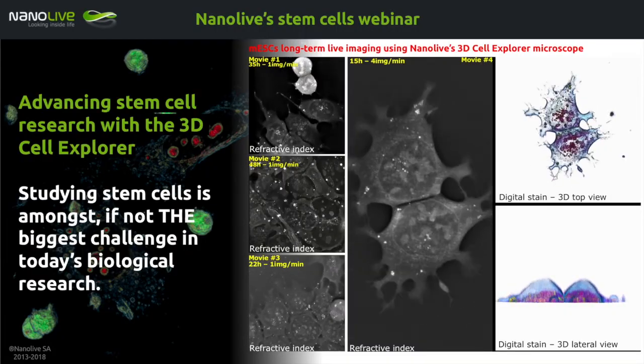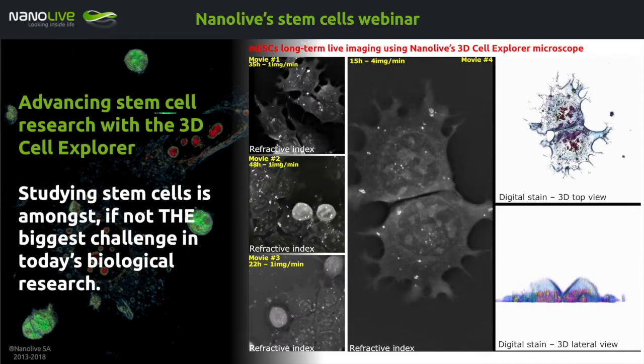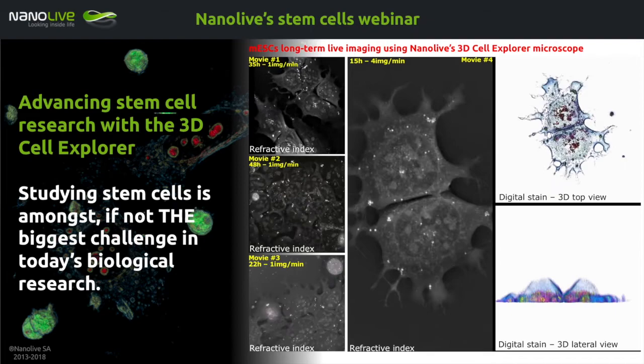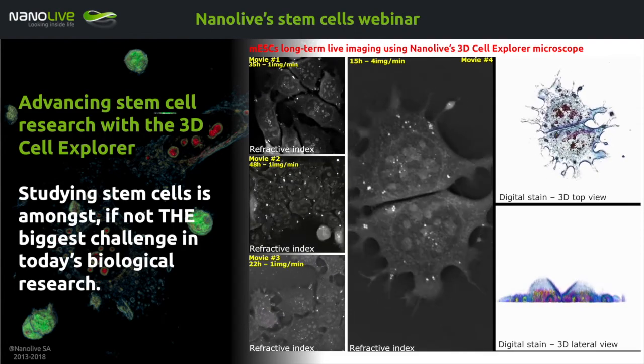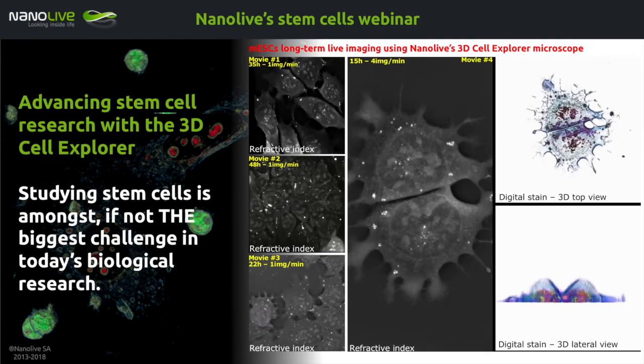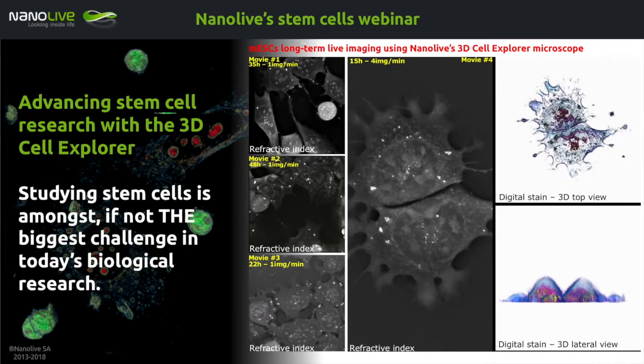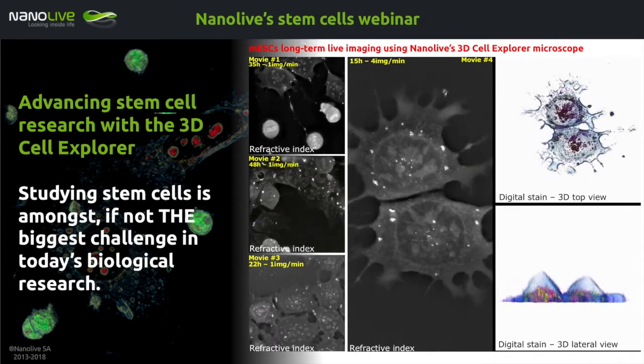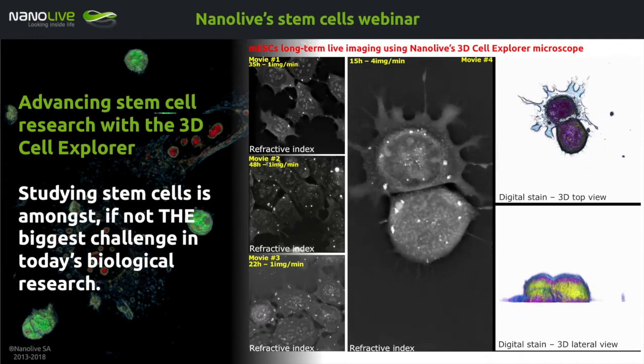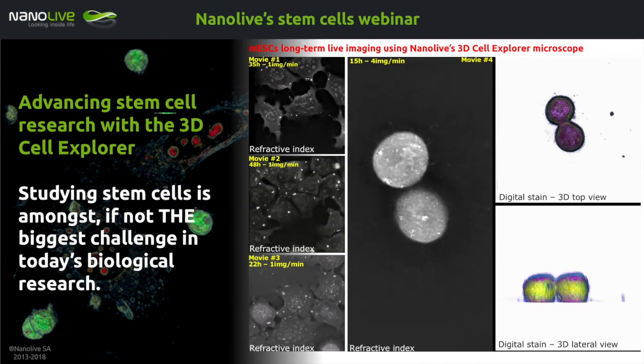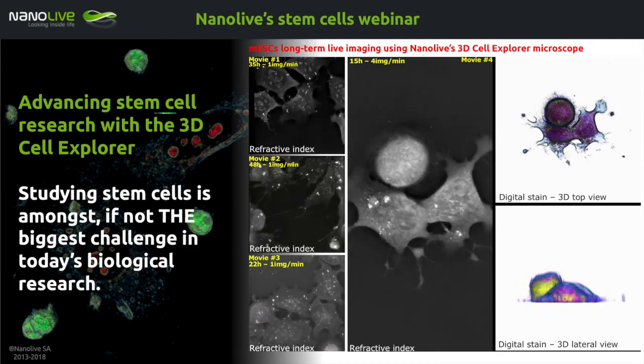I will now answer questions that we often get when presenting this work. The first question is: how long can you keep your cells alive under your microscope, and how long can you do such movies? The answer is simple: we can keep the cells alive under the microscope as long as you can keep them alive in a normal incubator in a tissue culture room. The reason is the microscope is not generating any phototoxicity, even for very sensitive cells like stem cells. Therefore, if your environment control is well set up — and we provide application notes for that — there is no reason you cannot keep cells alive as long as the well you're using for imaging is not totally crowded. At that time you would need to split the cells before they become too confluent.